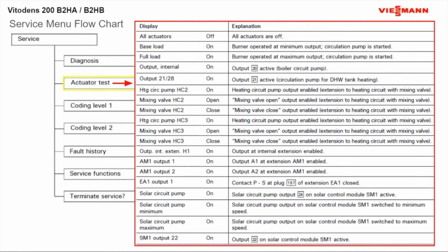You're going to go into base load and do a high fire and check your COs and your O2 levels on this base load. As well, we want you to do a high fire test to make sure that your CO2s and your O2s are in the accurate areas. Just remember with this boiler, there are no gas valve adjustments, because we have that beautiful Lambda Pro technology in this boiler, meaning that it will automatically set up almost perfect combustion every time it fires.